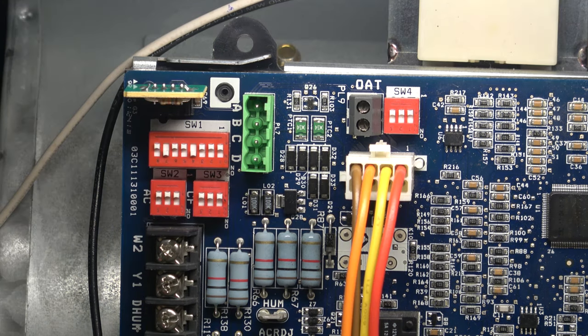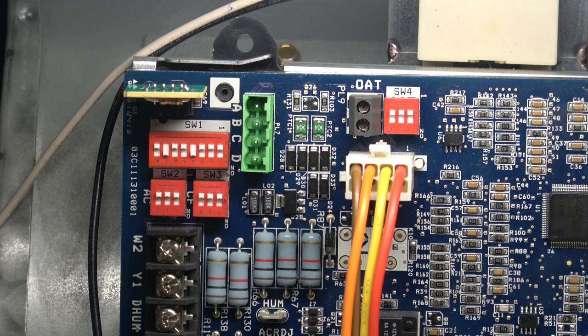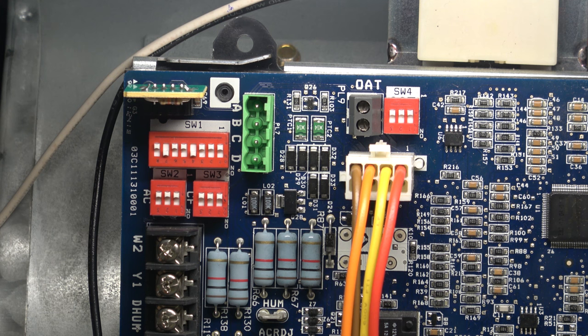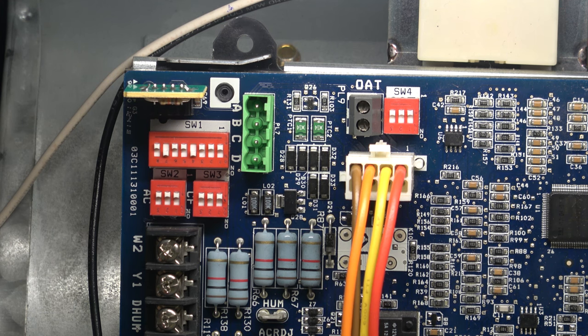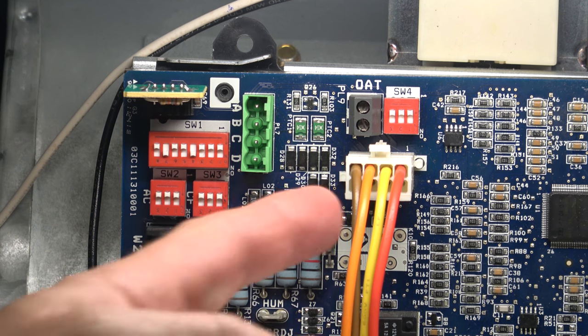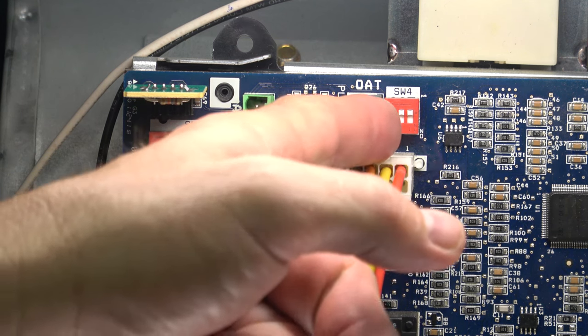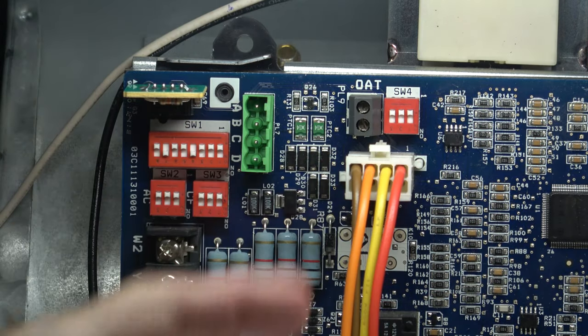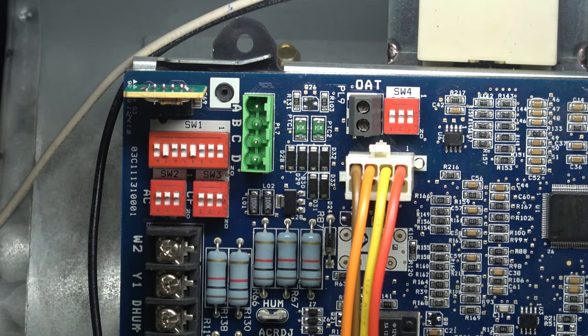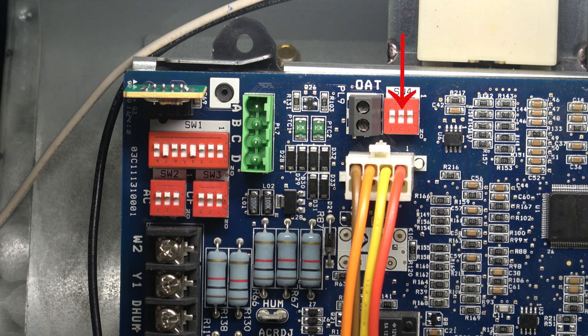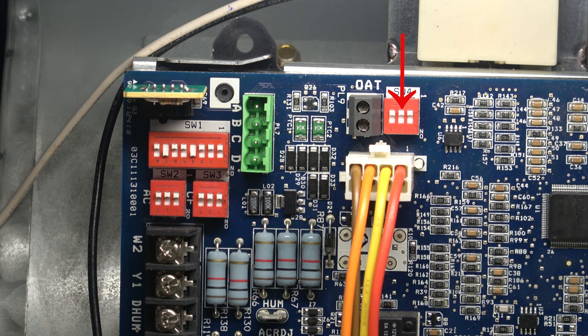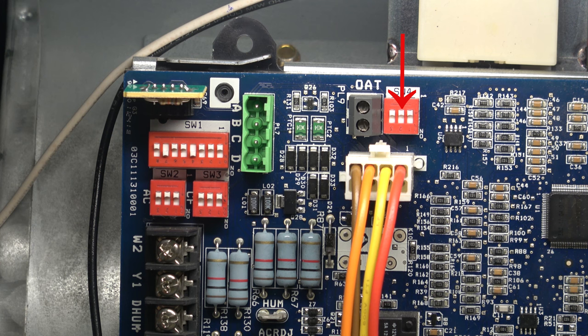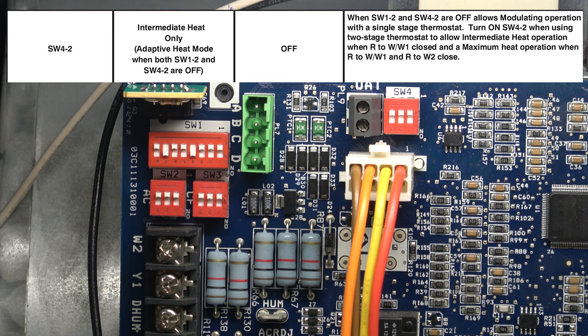The next switch is switch four. There are three setup switches on switch four. The first one is not used, so the normal position is off. Switch four is to the far right, about center of the board towards the top. Switch four number two, off is the normal position. This is used in conjunction with switch one number two. Switch one number two and switch four number two, both off, allows modulating operation with a single-stage thermostat.